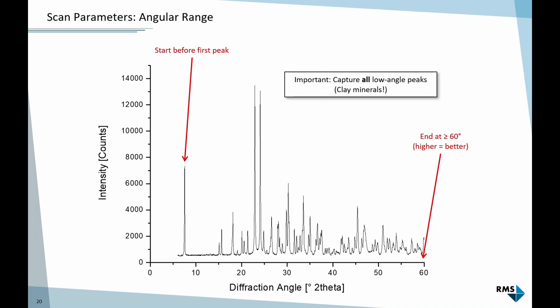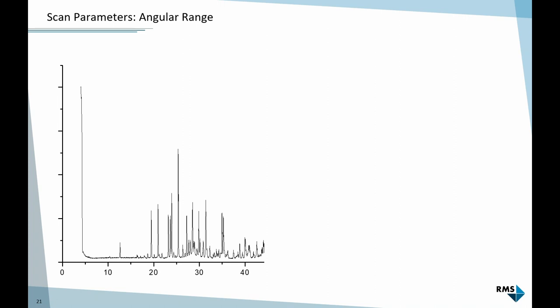How low should you start? What we see here on the left is the primary beam we start to measure - scattered radiation directly from the primary beam. This is no useful information. At some point you'll see a sharp increase of intensity and you know you're too close to the primary beam, almost at zero. Your primary beam almost goes directly into the detector - we don't need that. If we really hit the primary beam at zero degrees, we would damage the detector. So we don't want that. This is a bit too much.